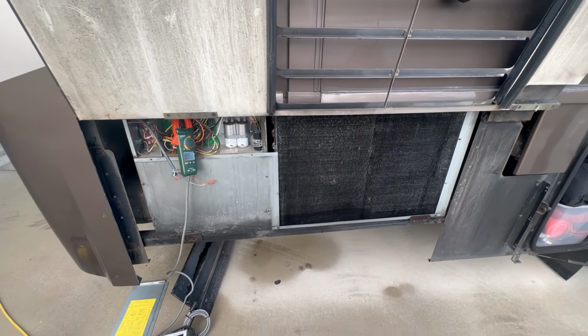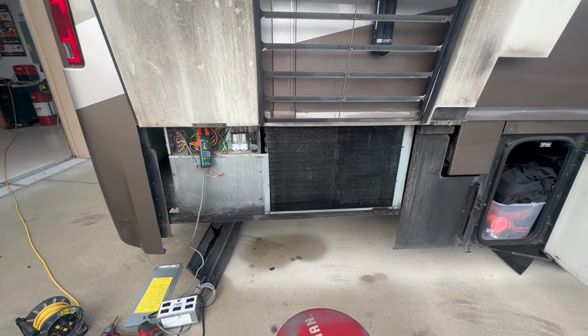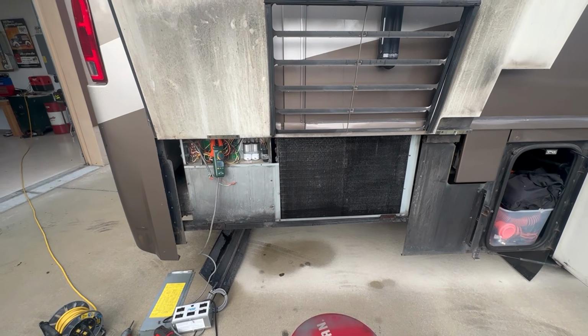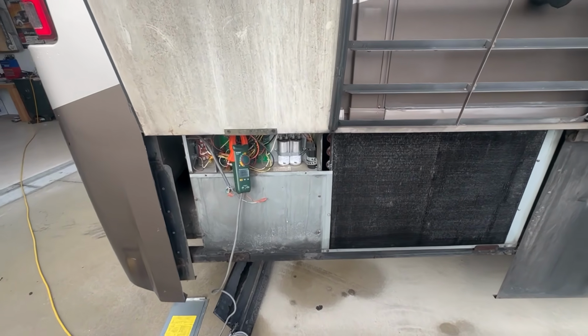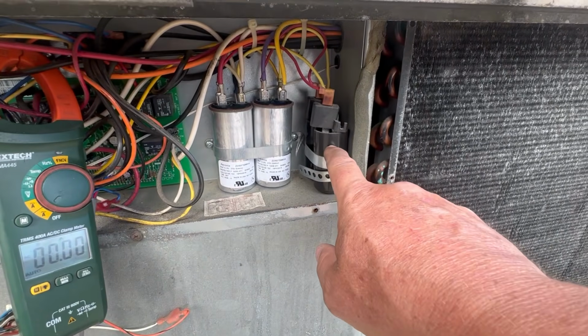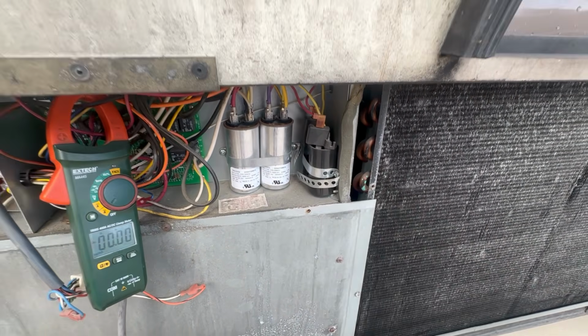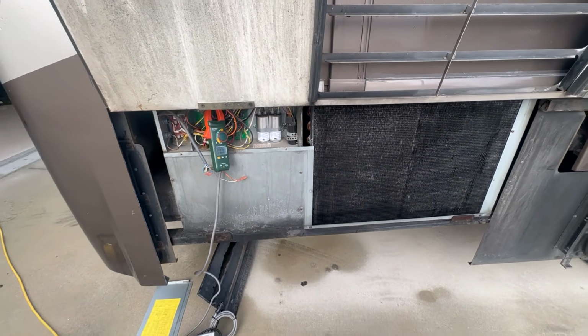This unit doesn't look like it's ever been out, so we're going to go ahead and pull it out, do a clean, because that could be a coil that's real dirty or nasty. And then we're going to check these caps out real good because that low amp draw very well could be one of these caps. So we're going to pull this out and give it a good bath.